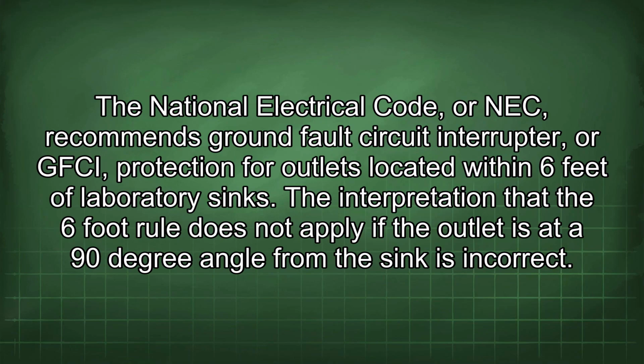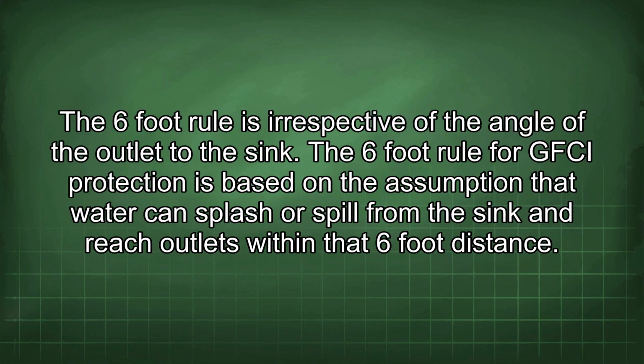The National Electrical Code, or NEC, recommends ground fault circuit interrupter, or GFCI, protection for outlets located within 6 feet of laboratory sinks. The interpretation that the 6-foot rule does not apply if the outlet is at a 90-degree angle from the sink is incorrect. The 6-foot rule is irrespective of the angle of the outlet to the sink. The 6-foot rule for GFCI protection is based on the assumption that water can splash or spill from the sink and reach outlets within that 6-foot distance.